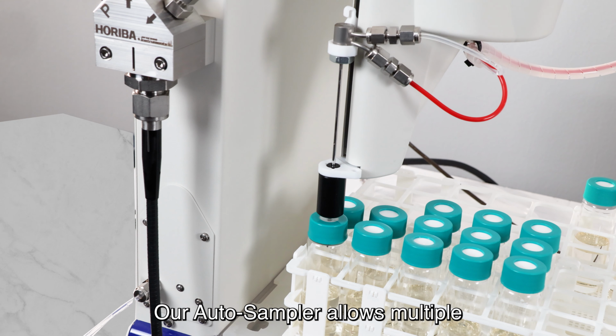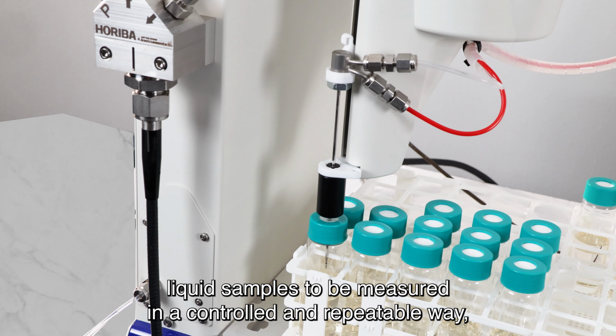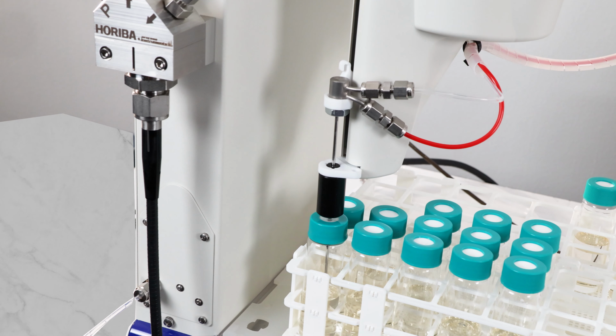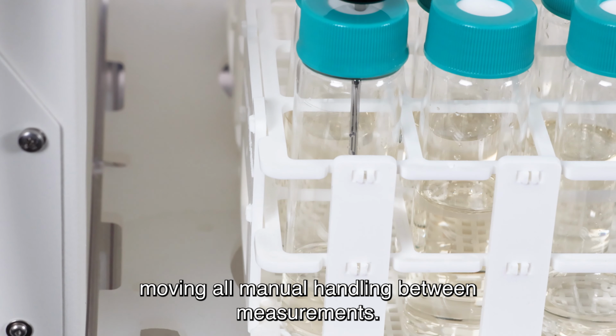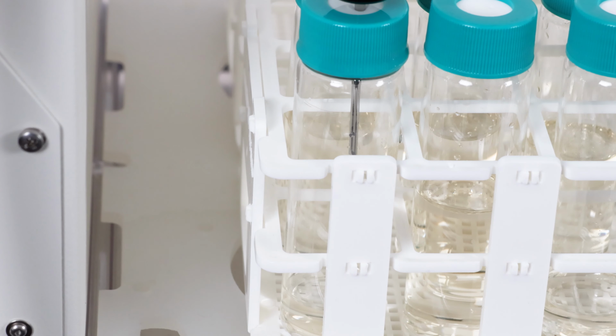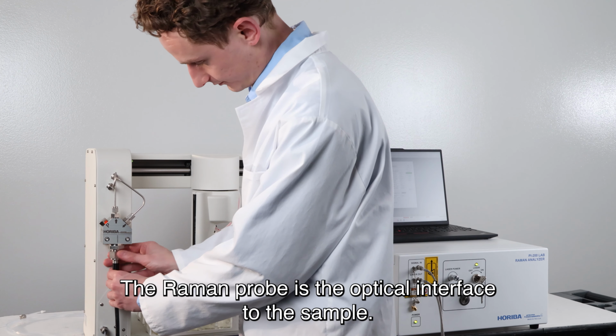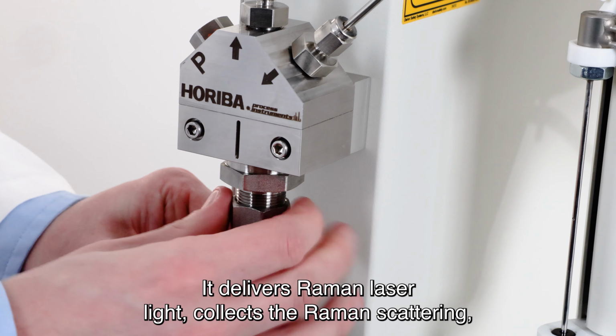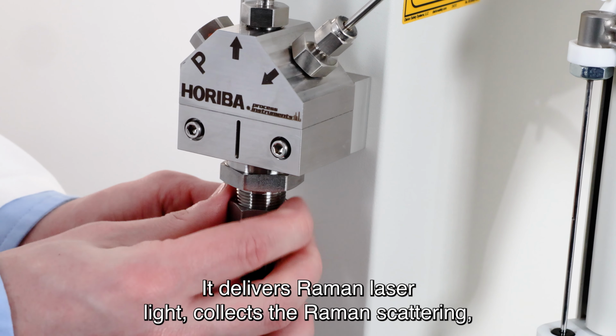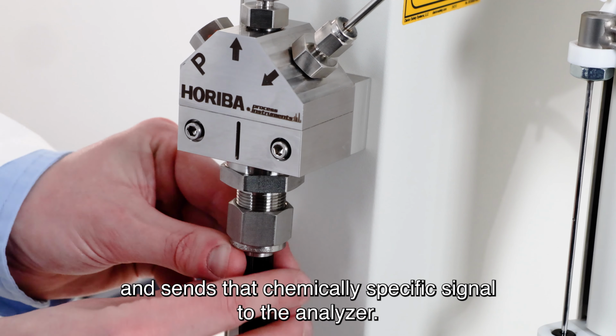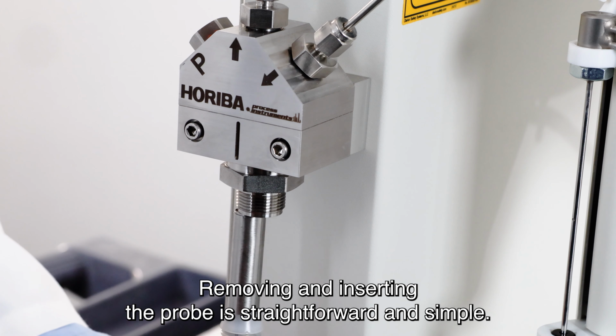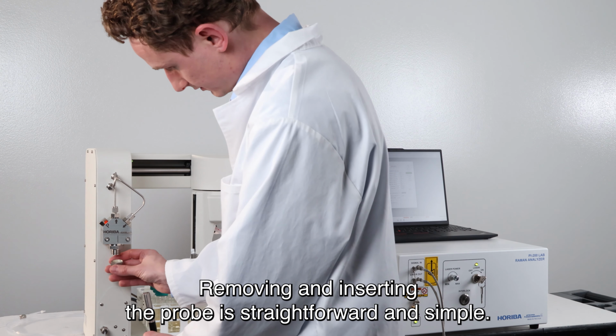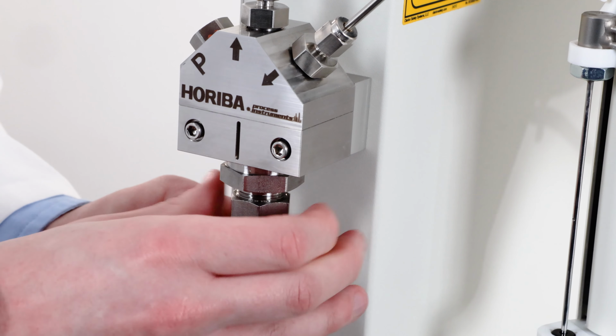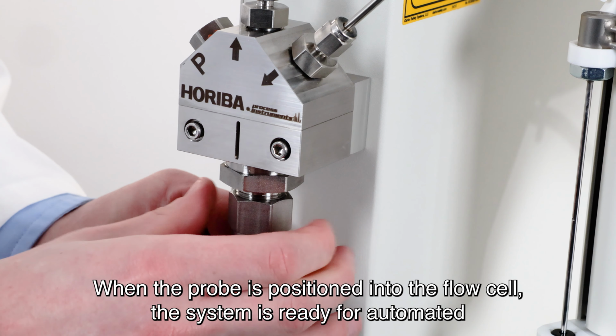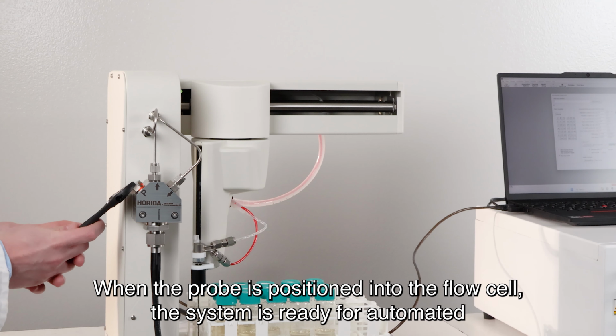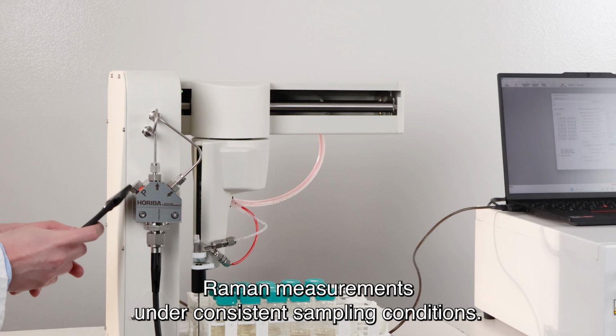Our autosampler allows multiple liquid samples to be measured in a controlled and repeatable way, removing all manual handling between measurements. The Raman probe is the optical interface to the sample. It delivers Raman laser light, collects the Raman scattering, and sends that chemically specific signal to the analyzer. Removing and inserting the probe is straightforward and simple. When the probe is positioned into the flow cell, the system is ready for automated Raman measurements under consistent sampling conditions.